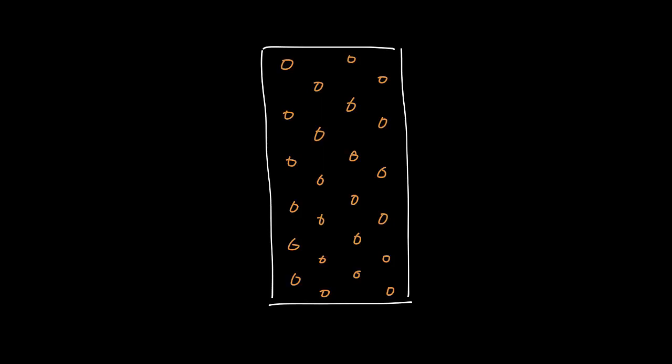Now if you look down these rows you can see there's a row here, that's row one, row two, row three, and row four, so there are four rows of tubes in our water coil. And if you count how many tubes they are high, you can see each row has six tubes, so it's six tubes high. So this is a four row water coil that's six tubes high.